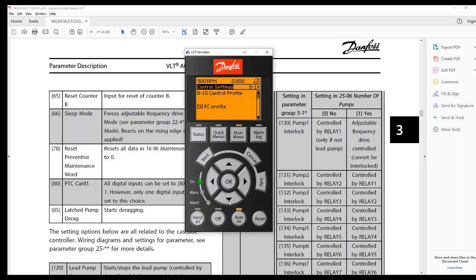in the drive, as far as the control words, we have, that's the status word, and we can configure control word bits. So these are the bit numbers, and there's the default, but I can command that DERAG. I can set a certain bit, change its function. So bit 12, which I think is just like control a relay, I can change that to trigger DERAG with start through serial. So if he's not hardwired, he's doing things through Ethernet, Ethernet IP or DeviceNet or what have you, you can configure the drive's control word bits, like say he's not using the relays, or there's also a couple others that change presets, he's not using them. We can edit the bit to do another function like DERAG here too through the serial.